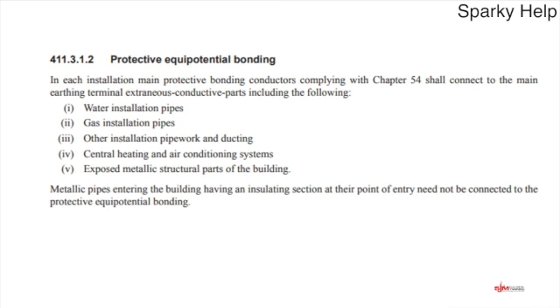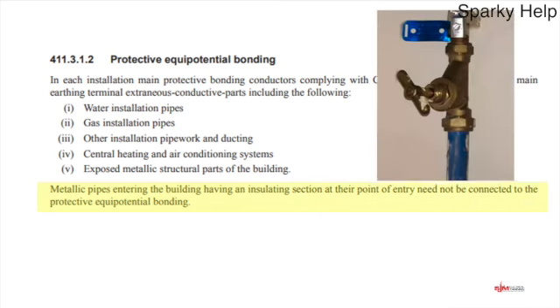There is a point to remember, and I said I'd come back to it, and this is it. And they've added this in as an addition to this 18th edition, which most people are aware of now, and that is metallic pipes entering the building having an insulating section at their point of entry need not be connected to protective equipotential bonding, because they do not introduce an earth. Therefore, they're not extraneous conductive parts.